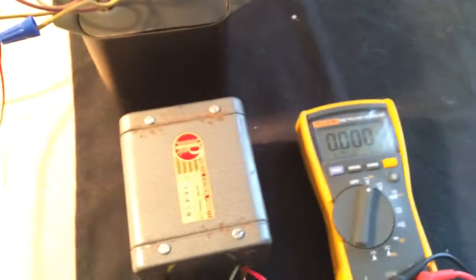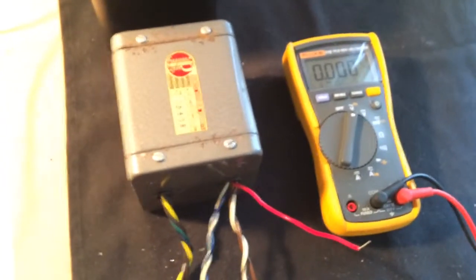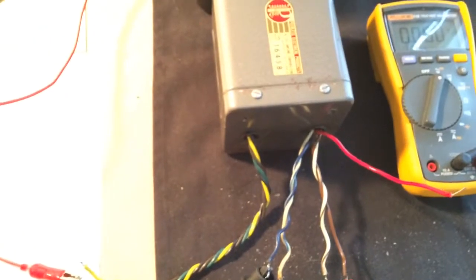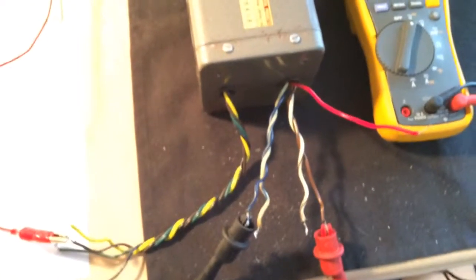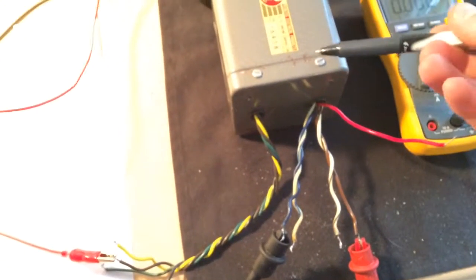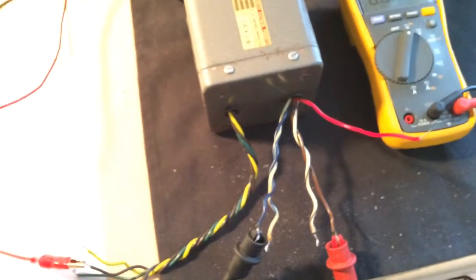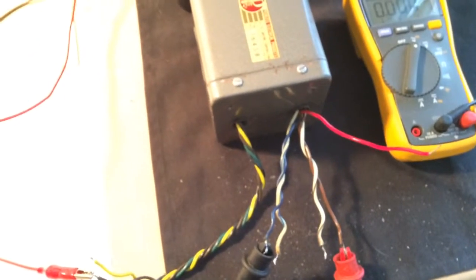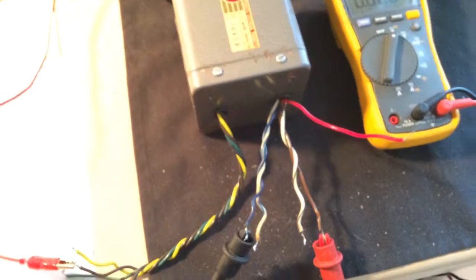I've also measured continuity between the primary and the secondary windings and everything's good there. I've also taken the lead of each of them to the chassis and I had no continuity. So I believe I don't have any shorts to the core or the case or anything like that.